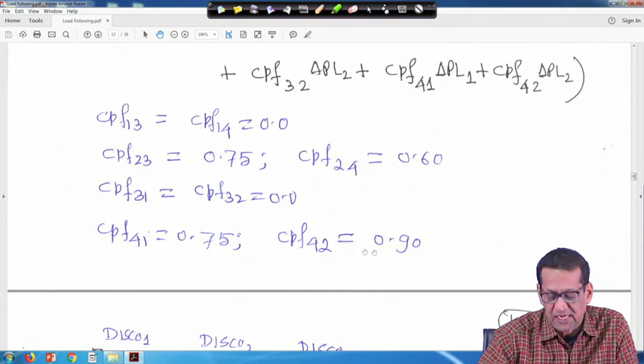So, now delta P tie 1-2 scheduled is equal to CPF 13 delta PL3 plus CPF 14 delta PL4 plus CPF 23 delta PL3 plus CPF 24 delta PL4, all in bracket, minus, in bracket, CPF 31 delta PL1 plus CPF 32 delta PL2 plus CPF 41 delta PL1 plus CPF 42 delta PL2. Bracket close. So, CPF 13 is equal to CPF 14 is equal to 0, CPF 23 is 0.75 and CPF 24 is 0.6, right. CPF 31 and CPF 32 both are zeros, from the DPM that we have taken, and CPF 41 is 0.75 and CPF 42 is 0.9.